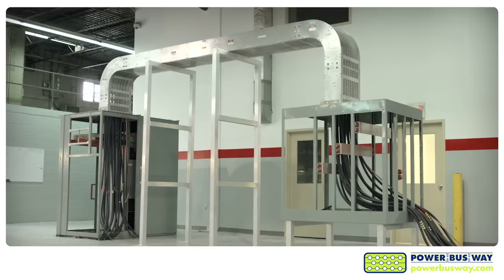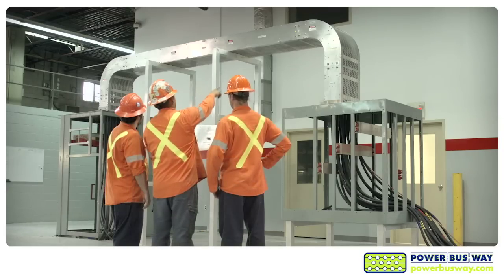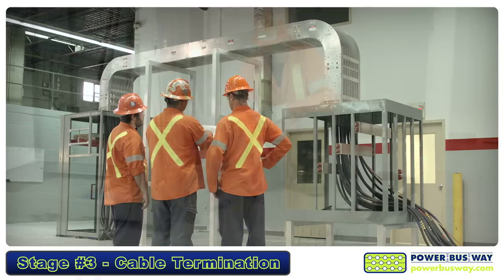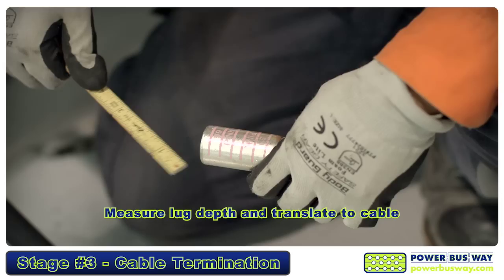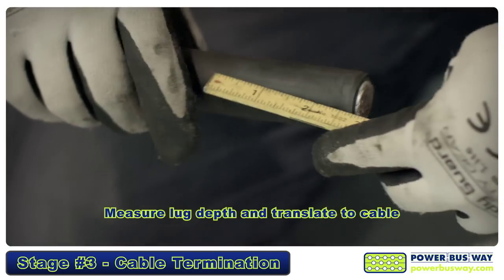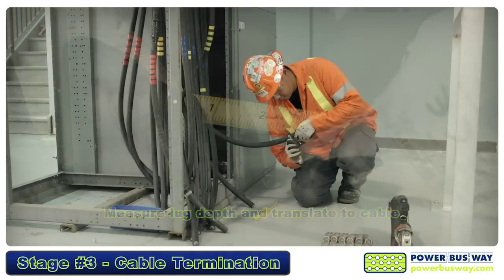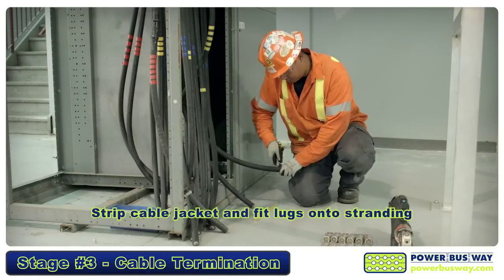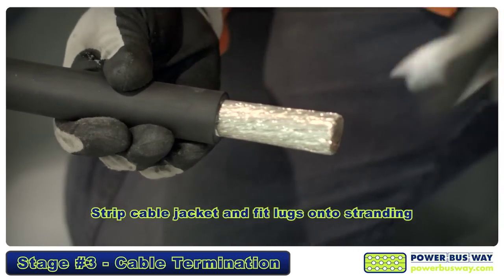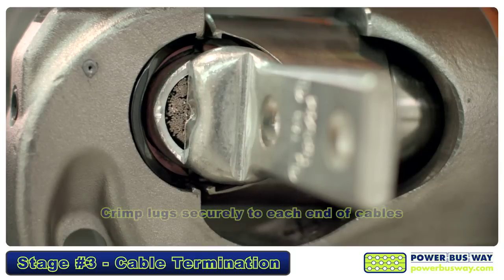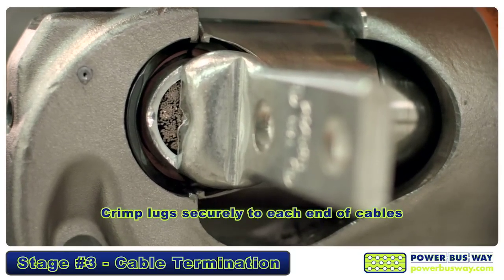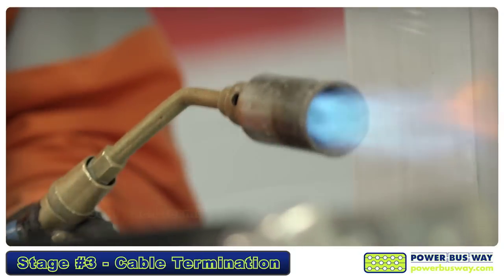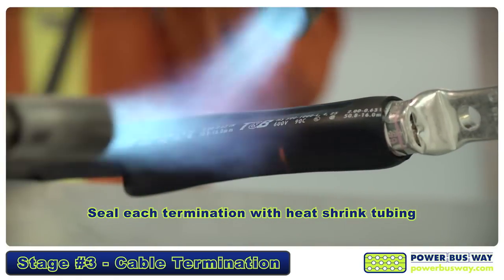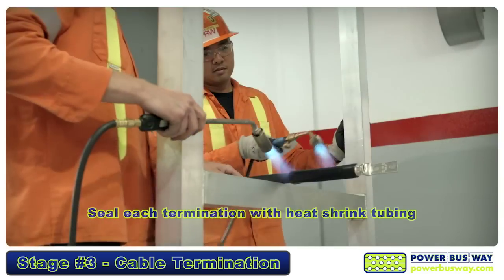With the enclosure fully loaded, it's time for Stage 3 of the installation: cable termination. Measure the interior depth of the provided lugs and translate the depth measurement to the cable. Strip the cable jacket before fitting each lug onto the cable stranding. Using the specified tools and dies, crimp the lug securely to each end of the cables. It's recommended that heat shrink tubing be used to seal each termination. Be sure to comply with all safety standards when completing this step.